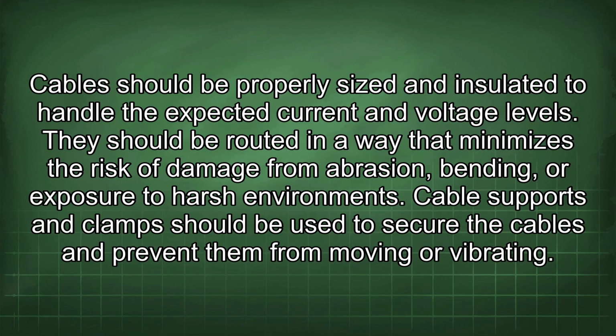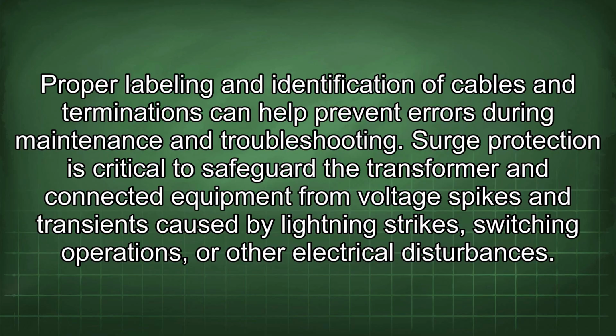Proper cable management is also crucial for safety and reliability. Cables should be properly sized and insulated to handle the expected current and voltage levels. They should be routed in a way that minimizes the risk of damage from abrasion, bending, or exposure to harsh environments. Cable supports and clamps should be used to secure the cables and prevent them from moving or vibrating. Proper labeling and identification of cables and terminations can help prevent errors during maintenance and troubleshooting.